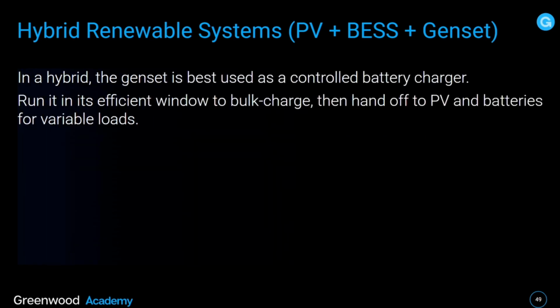In a hybrid situation, the genset is best used as a controlled battery charger. Run it in its efficient window to bulk charge, then hand off to PV and batteries for variable loads. And this, of course, depends on the kind of battery that you're charging. So obviously a lithium battery has a different charge regime compared to, say, a gel-based lead-acid battery.